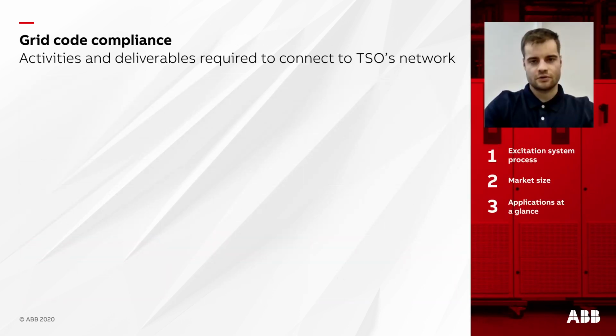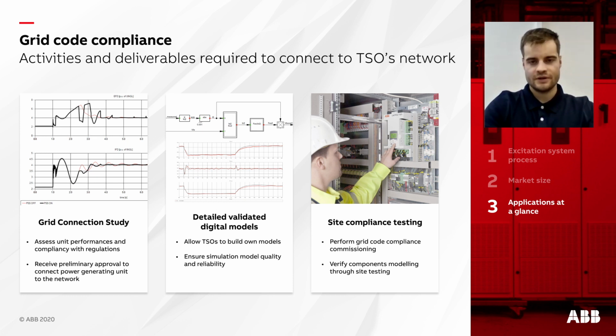A short word about grid code compliance. You've probably heard about it if you're in a country with strong regulations for connecting a unit to the grid. Grid code compliance is mainly needed when connecting a new unit to the grid, or if you've renewed the control part and need to prove your unit is still compliant with the TSOs - transmission system operators - who have, depending on the country, strict regulations about the behavior of your excitation and synchronous machine when connecting to the network.